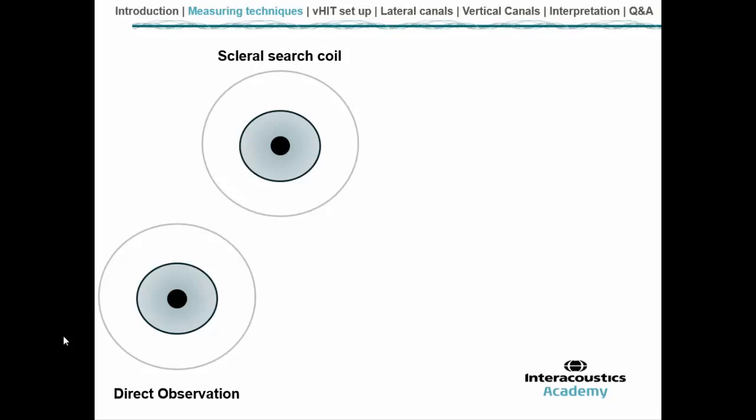After direct observation, a different method was developed known as the scleral search coil. This involves placing a contact lens on the patient's eye and placing them in a large magnetic field, which provides a very sensitive measure of eye movement in relation to head movement. Although this is a very sensitive test, it's just not very clinically friendly. The contact lens is very uncomfortable and patients will not tolerate it in a day-to-day clinical environment. The equipment is so bulky, the calibration process and expense are just too much for a general clinical environment.